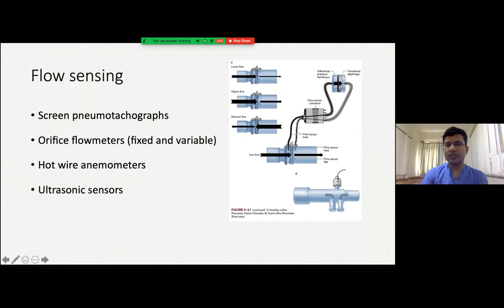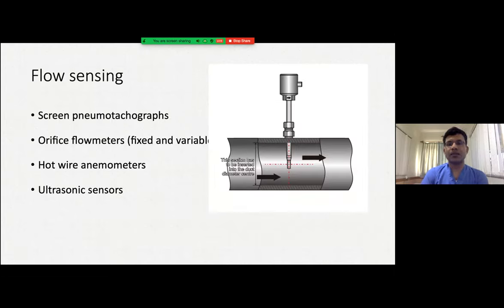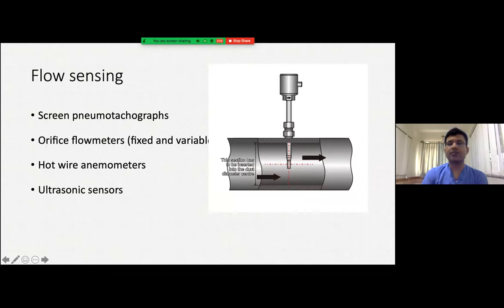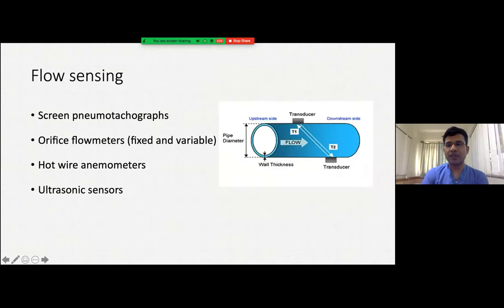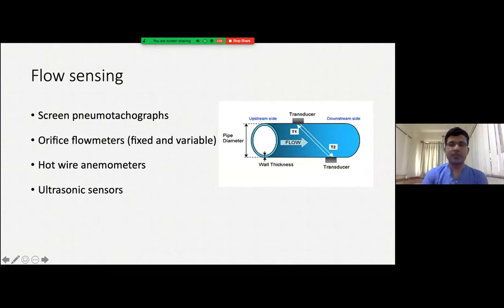There are also fixed orifice flow meters. Another method is the hot wire anemometer, where a metal such as tungsten has a baseline temperature. As gas flows across this metal, the temperature falls, generating an electrical signal interpreted as flow. We also have ultrasonic sensors where ultrasonic radiation is sent from transducer to transducer across the flow — depending on the velocity of flow, the signals differ, and this gives the flow reading.